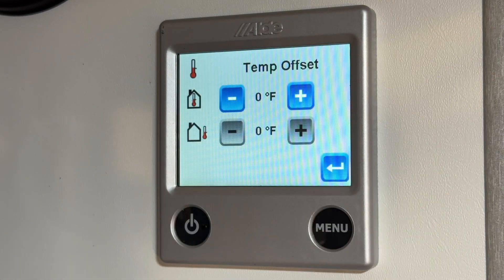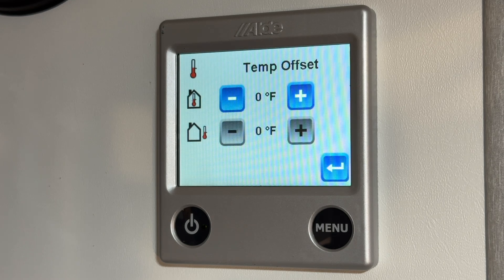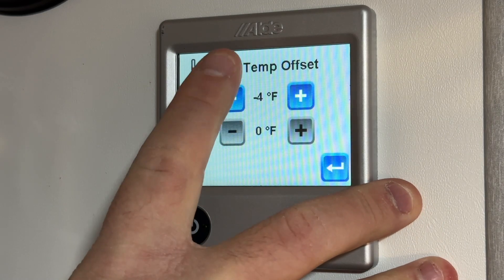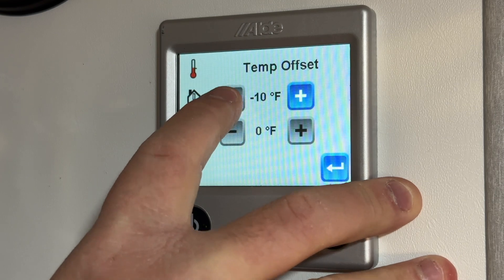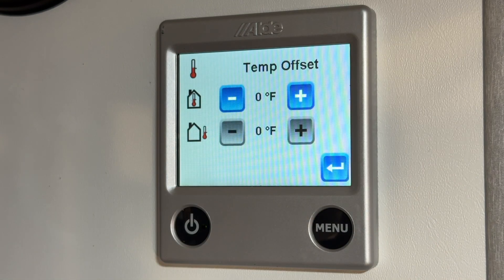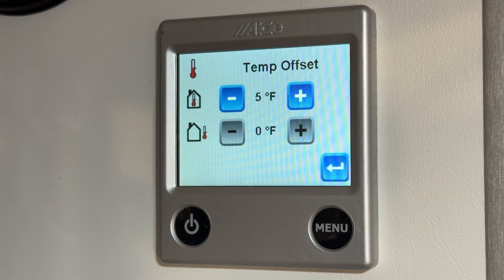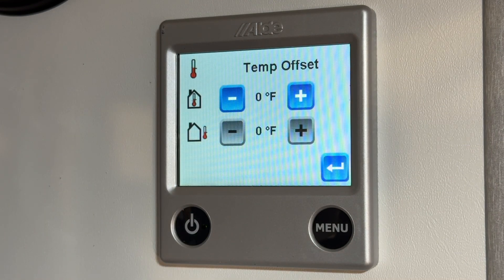Next is the temperature offset. We don't have an exterior probe sensor so it's interior only. This is used if you notice the Alde is reading a little off compared to a handheld thermometer. So if the Alde was reading five degrees higher than it should be, you would go minus five — you can offset it up to 10 degrees in either direction. Vice versa, if the Alde is reading five degrees too cold, you would go up five. This is something great to do at the beginning: bring in a handheld thermometer and make sure it's matching the Alde for better accuracy.